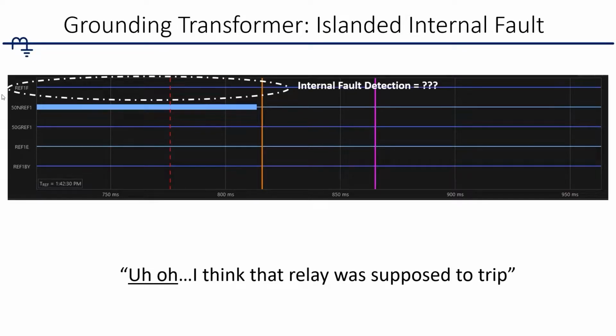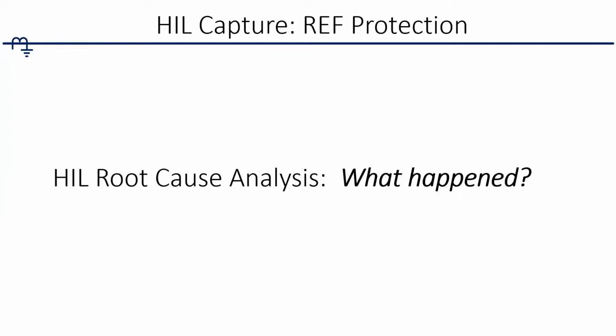Well, this is the internal fault detection. It did not pick up. So what do we do? And the younger engineer I was working with said, I think it was supposed to operate here, and it sat there for a while. I was waiting for it to trip, and it never did. It sat there for a good 10, 15 seconds running with a fault on it. So we paused and said, well, what happened? I mean, the symmetrical components are lining up. What's the deal? Why is this relay not operating for an internal fault?